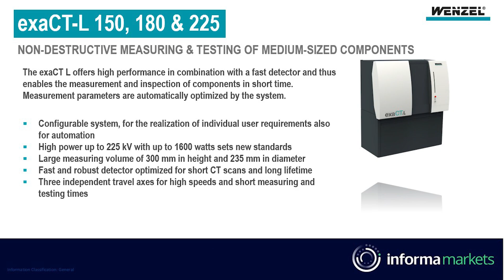The tubes have a very long lifetime. Our German engineers have provided these X-ray tubes and detectors so that we're looking at a useful life of up to 10 years. And some of the machines have been installed and working for much longer than that without a tube replacement. Actually, an X-ray tube is kind of like a light bulb. If you think of it that way, it has a filament and it has a bias to it. So as opposed to making light, it makes electrons which bounce off a target and create X-rays.